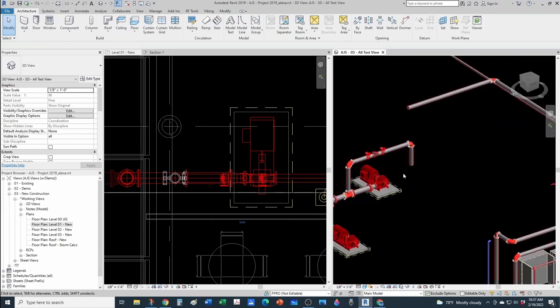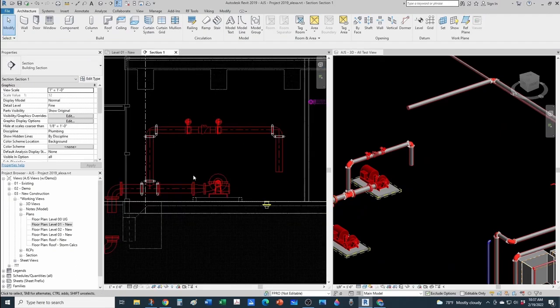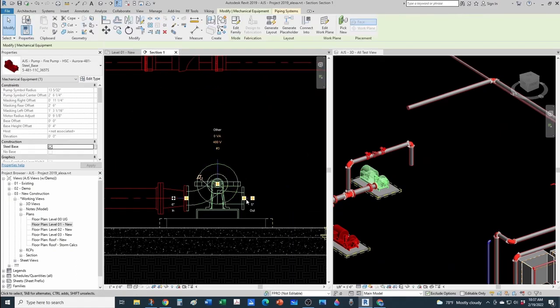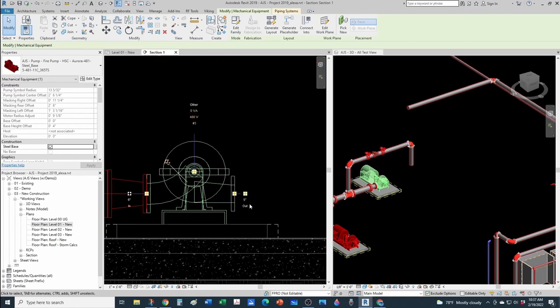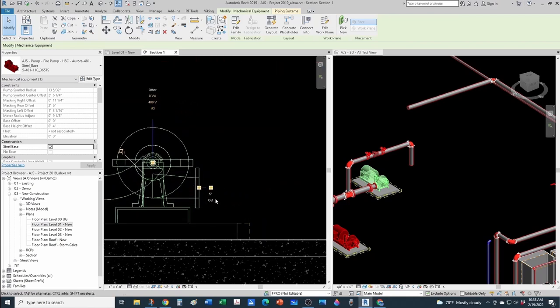And now let's keep going with our pump. So I'm gonna go to my section, and I'm gonna take my discharge line. You can notice that the discharge flange of this pump is 5 inches, and I need a 6-inch discharge. So in this particular case, I'm going to need that concentric increaser, but sometimes you will have a discharge flange of 6 inches, and then you can just go with that if you are with a 1000 GPM pump.